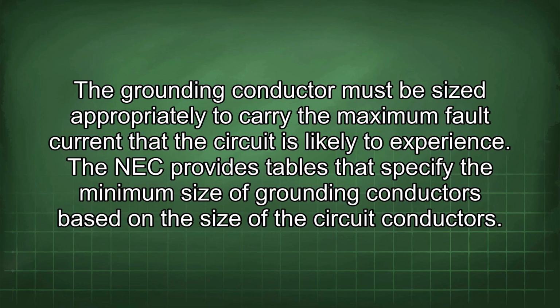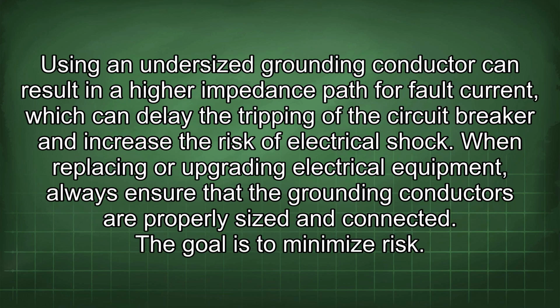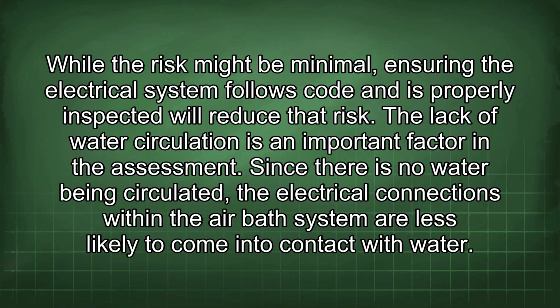The grounding conductor must be sized appropriately to carry the maximum fault current that the circuit is likely to experience. The NEC provides tables that specify the minimum size of grounding conductors based on the size of the circuit conductors. Using an undersized grounding conductor can result in a higher impedance path for fault current, which can delay the tripping of the circuit breaker and increase the risk of electrical shock. When replacing or upgrading electrical equipment, always ensure that the grounding conductors are properly sized and connected. The goal is to minimize risk. While the risk might be minimal, ensuring the electrical system follows code and is properly inspected will reduce that risk.